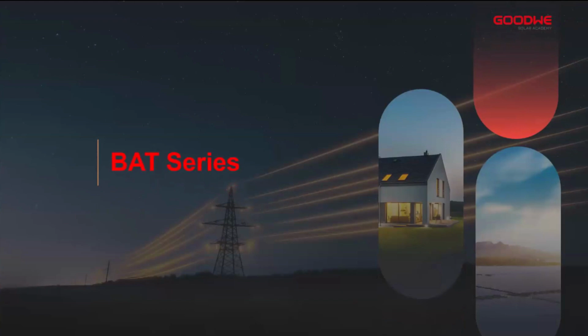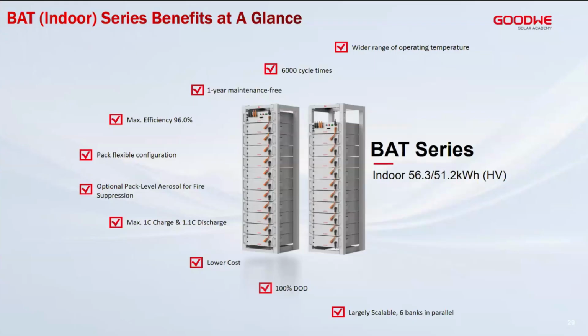the battery models that we have for this C&I market. What we have first off is the BAT series. Now the first BAT series battery that we have is the indoor battery. We have two variants. The first variant is the indoor, the biggest, has 11 modules, 56.3 kilowatt hour. And the next is the 51.2 kilowatt hour. Basically, it's just a difference in terms of number of battery modules. 56.3 will have 11 batteries, 51.2 will have 10 batteries.